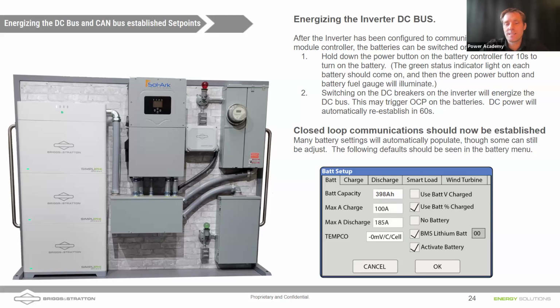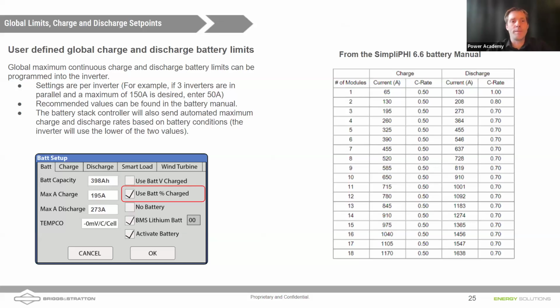So the settings on this screen are the global values, meaning solar plus any other source, like solar plus grid or solar plus generator, as Daniel said. Same on the discharge, right? If I'm discharging my batteries here, it's a global overall limit. So let's talk about what these limits should be for our battery stacks. Batteries have a continuous power limitation. They can surge, but that power is limited to safe values.